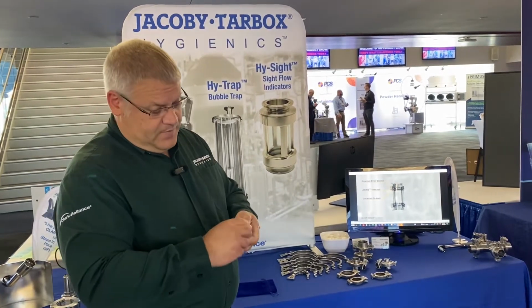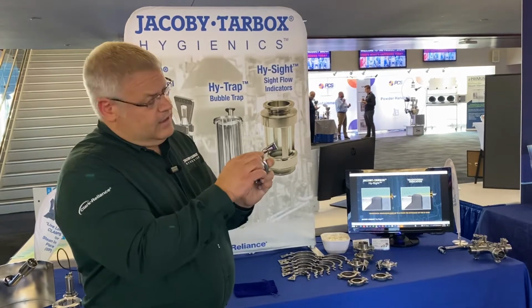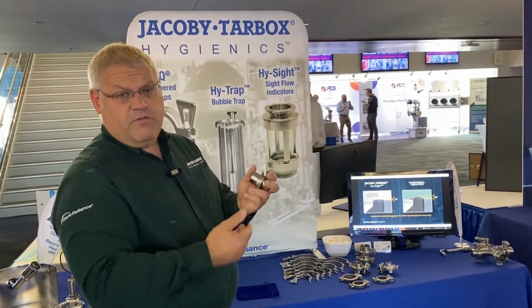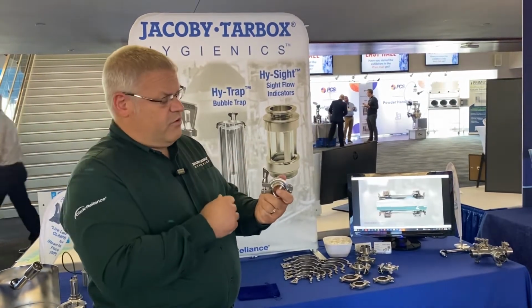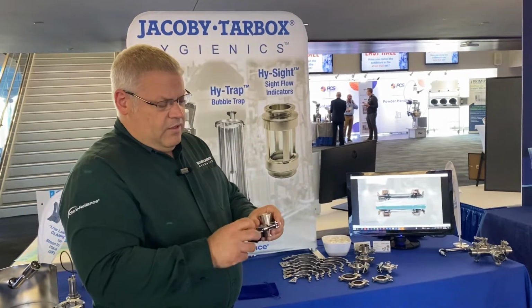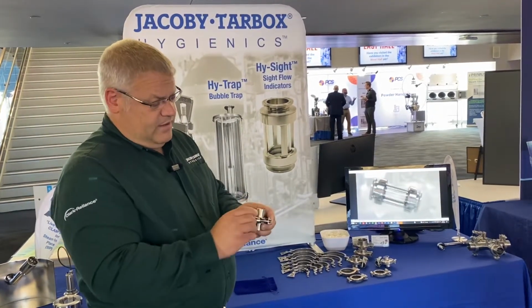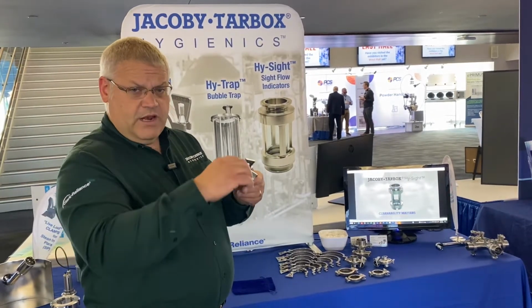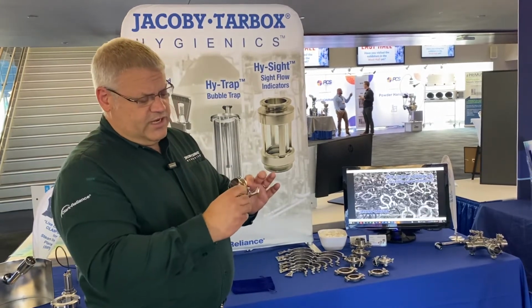the way around. You have to extend that swing bolt nice and far because the elongated edge of the arm then extends out, making it more difficult for that to come off if it were to loosen in vibrating service or thermal cycling. The boss on the nut also engages the recess on the clamp to ensure you've got perfect alignment.